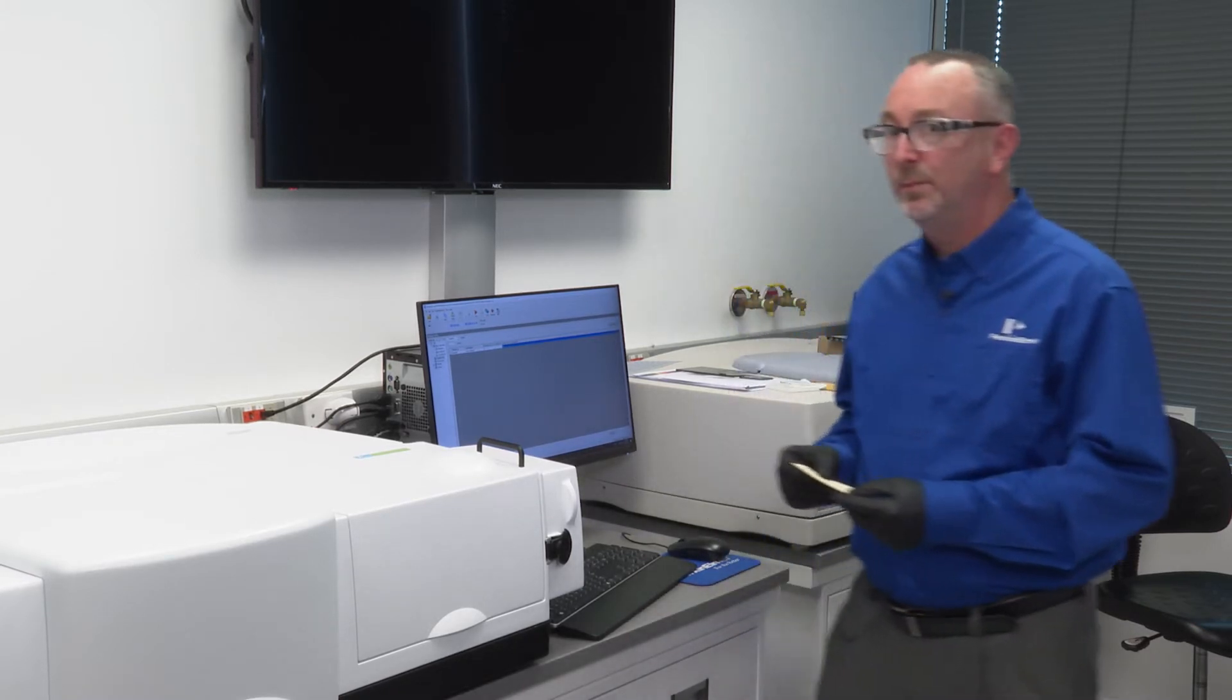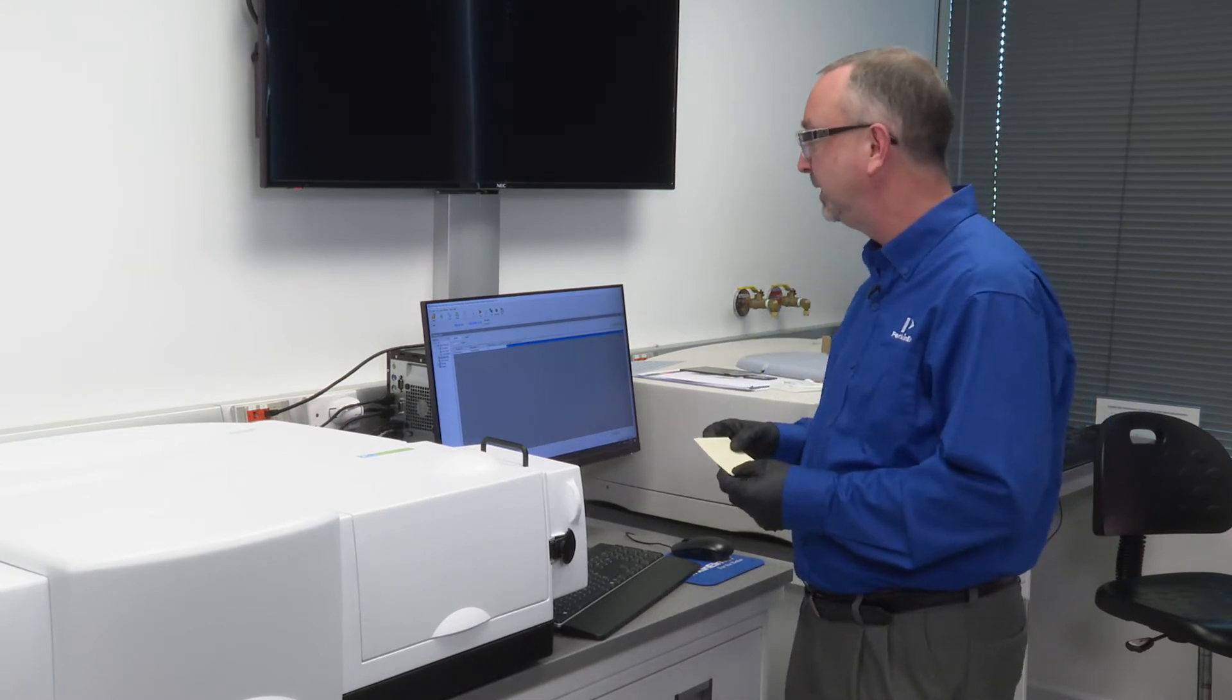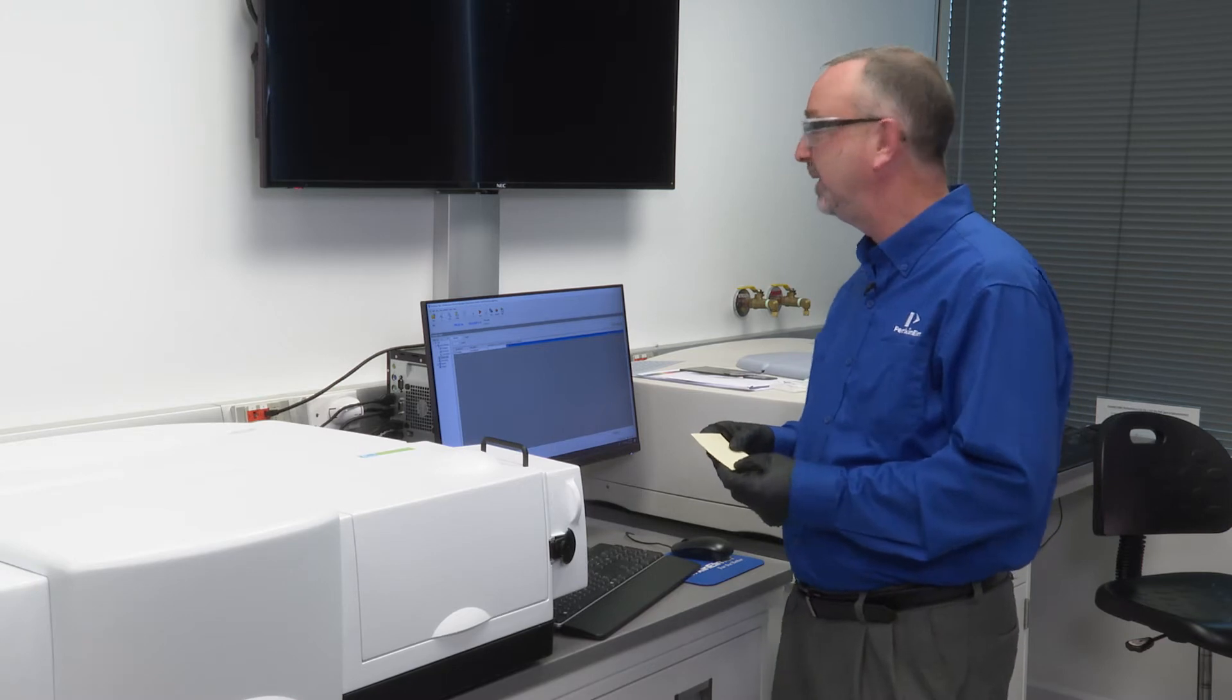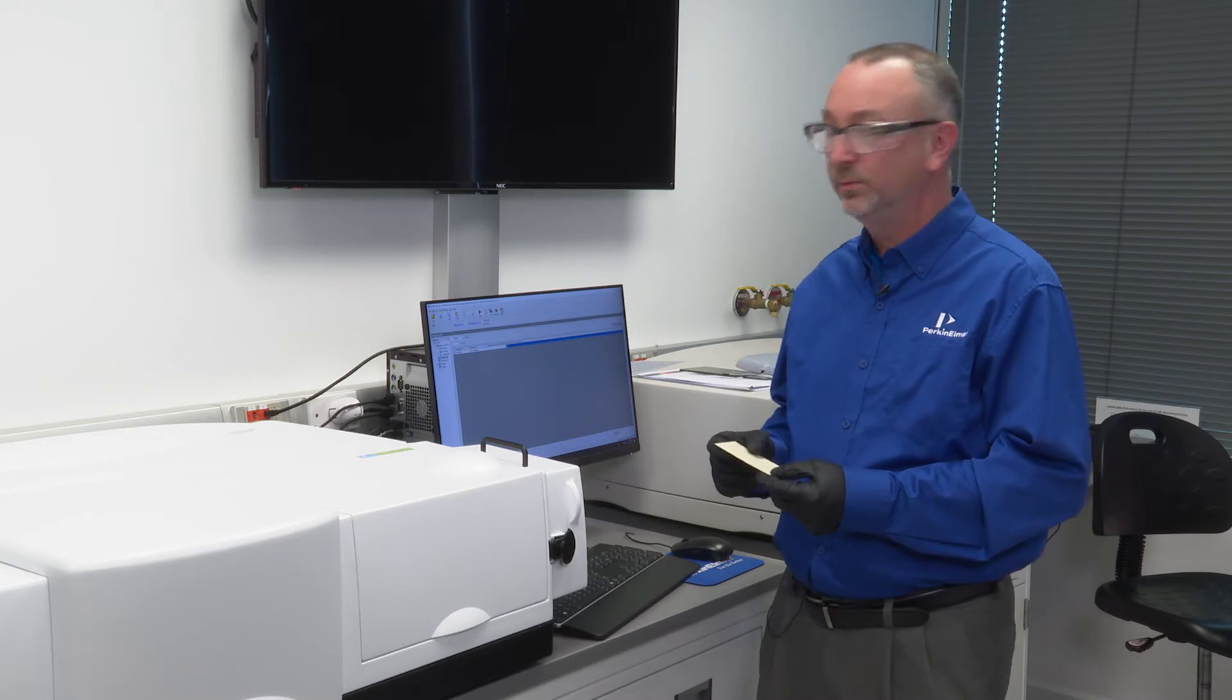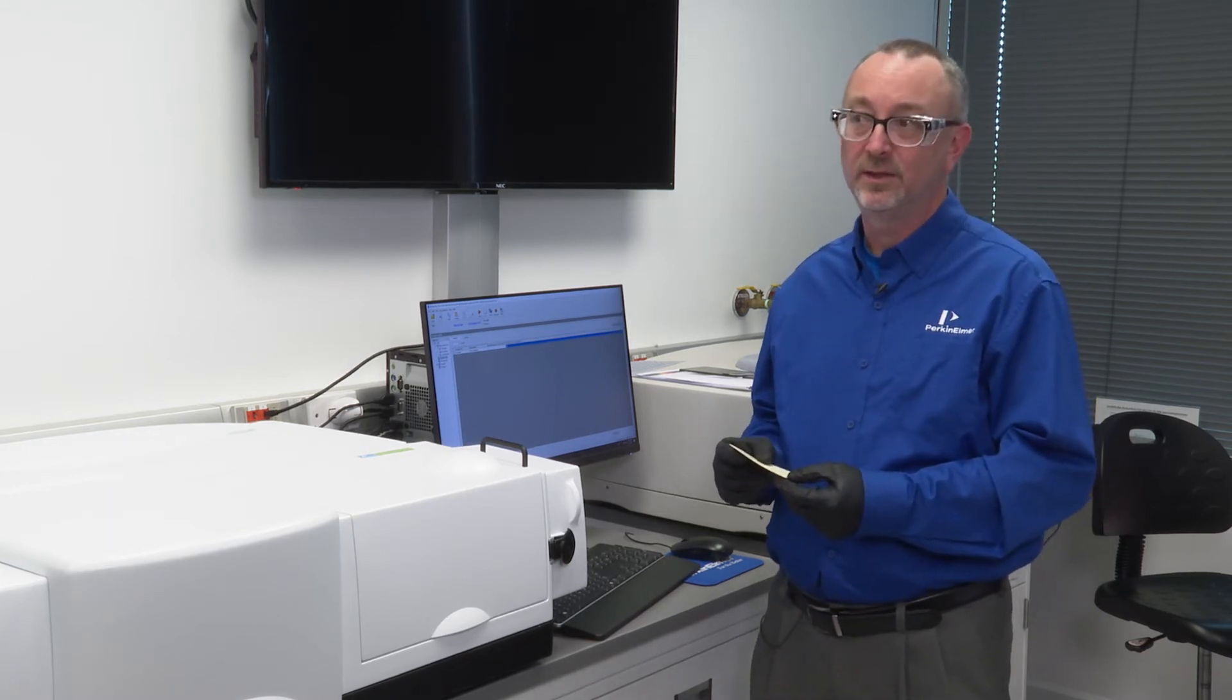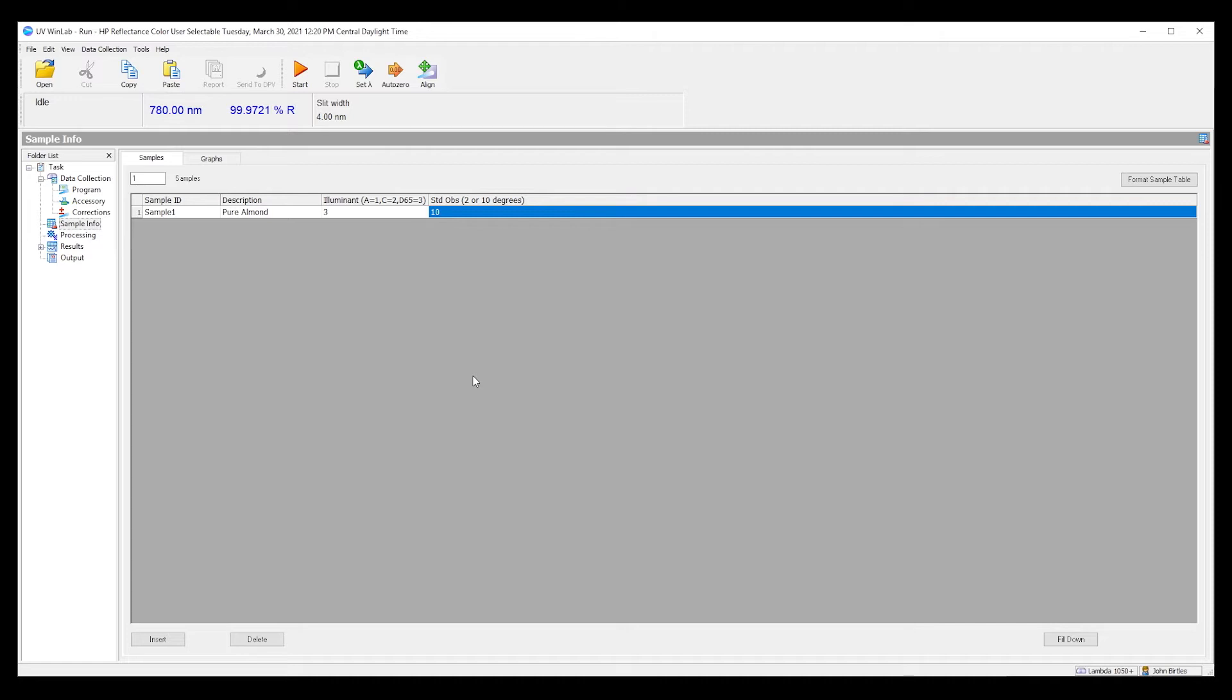Once we set up the method, we can define several components for the color calculation, including the illuminant type and the observer angle. These are typically 10 degrees for the observer angle and for the illuminant D65, i.e. sunlight or daylight, is typically used. There are other options as seen in the software here. More extensive calculation capabilities are possible, and we have an additional software package that can be extended to include those other variables.